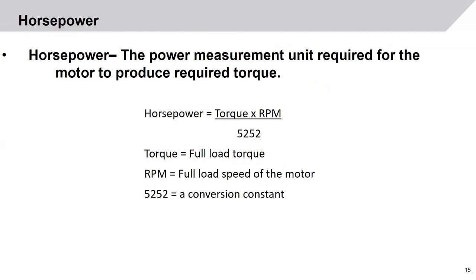One unit of measurement for motors is horsepower — the power measurement required for the motor to produce the required torque. It is the output of the motor. Horsepower is defined as torque times RPM divided by 5252. The torque is the full load torque required to move the load. The RPM is the full load speed of the motor — whether 3600, 1800, 900, and so forth. The value 5252 is a conversion constant in the electrical world.